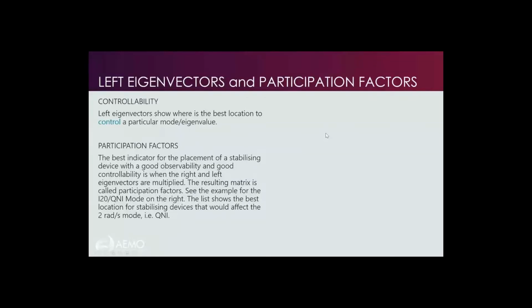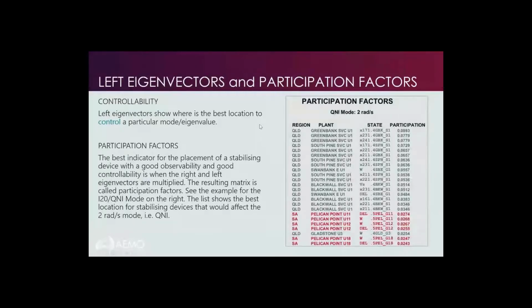So here, in the next slide, I want to show you participation factors. We said that the left eigenvector shows you where is the best location to control a particular mode or eigenvalue. So if we multiply the left and right eigenvector, we get participation factors. For QNI, what we get is that the best location to damp this 2 radians per second mode is at Greenbank, South Pine SVC, Blackwall SVC, and Swanbank E. On some of these devices, Swanbank E has a power system stabilizer, while Blackwall and Greenbank have power oscillation damping devices.